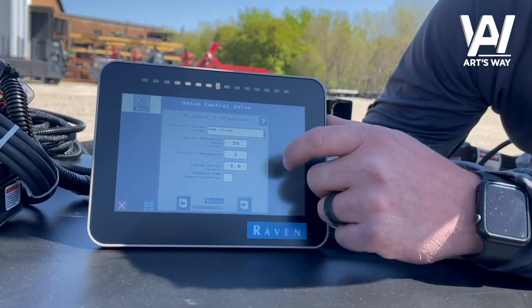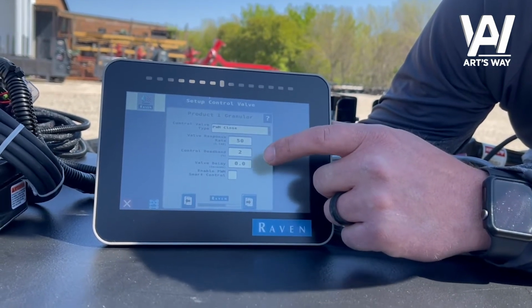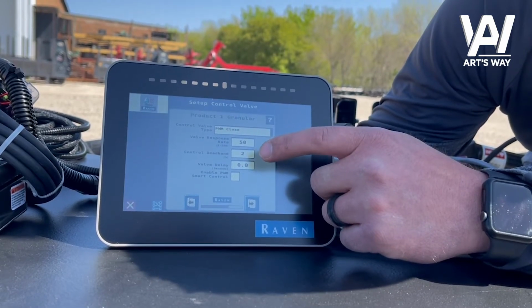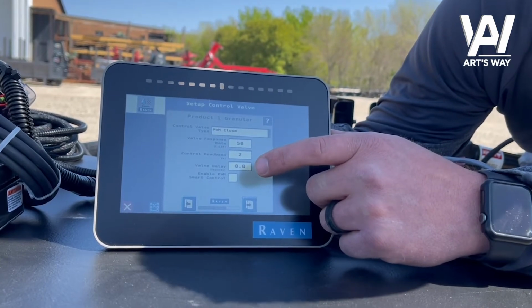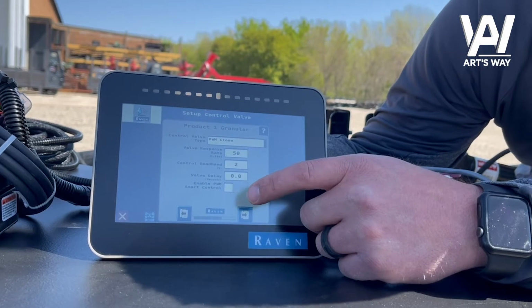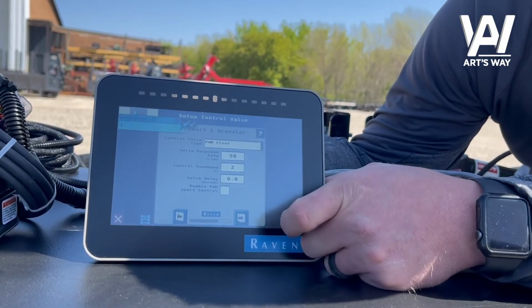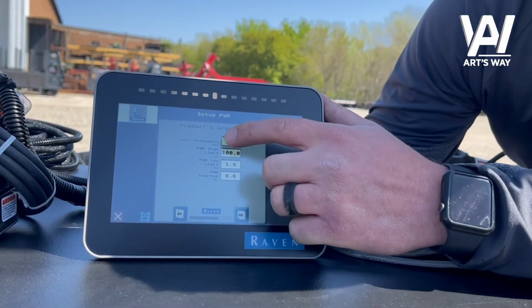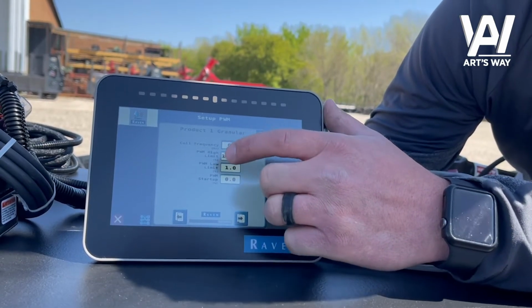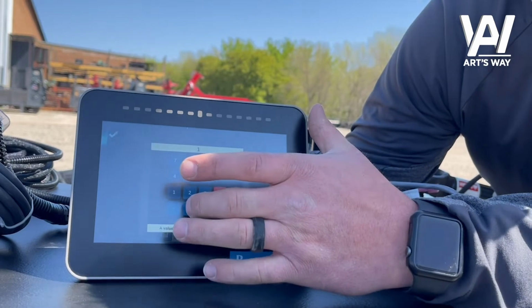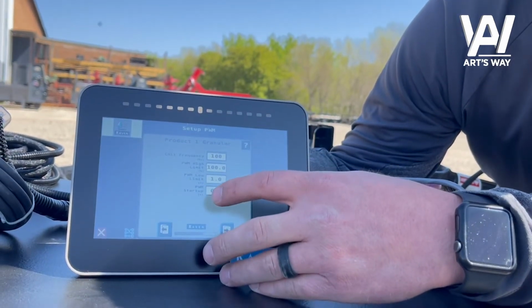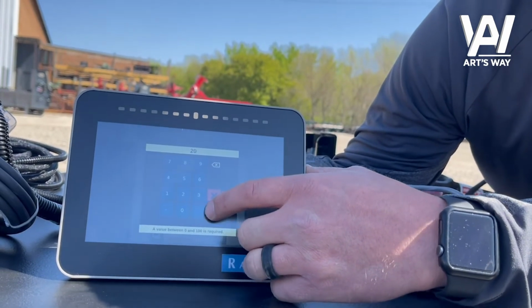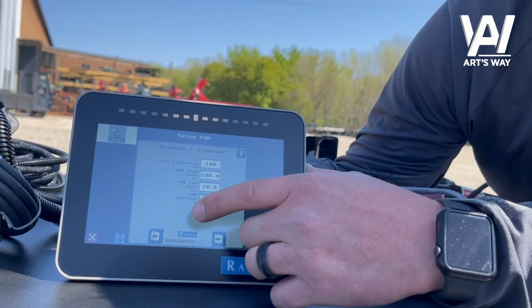Our valve type will run as PWM closed. The response rate defaults to 50. Control valve deadband defaults to 2. Valve delay remains at 0, and will run with the smart PWM disabled. Coil frequency for this particular PWM cartridge is preferred at 100. Our PWM low limit will probably run around 20. These are user adjustable per system, but this is a pretty good starting point for each. And then we'll put our startup as 25.